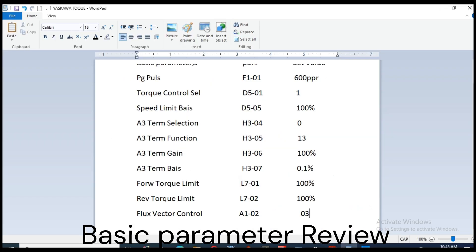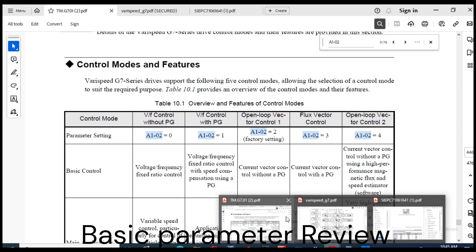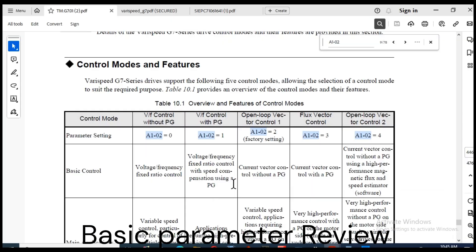Now we start. Parameter Review. Basic Parameter. A1-02 control method selection is set to 3 for flux vector control.